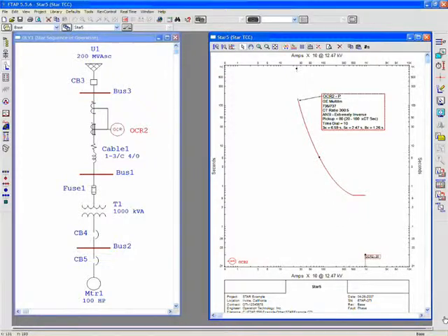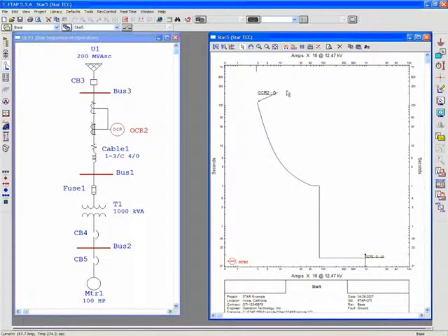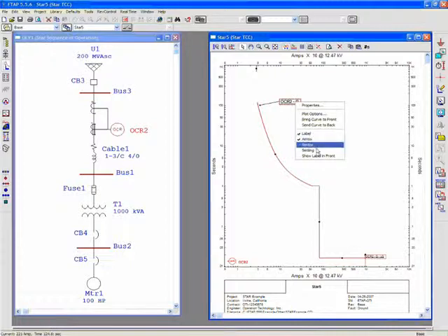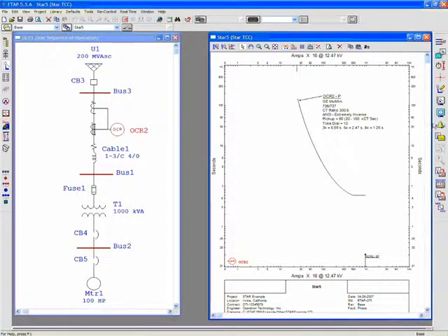As you see on your right-hand side, there's a number of tools here. There's a phase curve, there's a ground curve for the same relay. For this case, we want to test the phase curve. So again, this is the ground curve of the same relay shown on the same TCC, and we have the phase. We want to test the phase curve of this device.